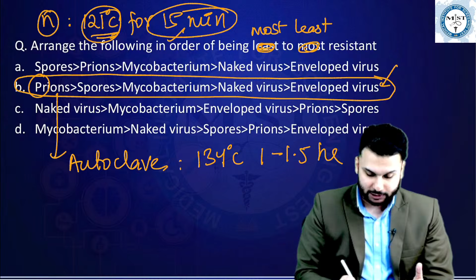But now, when we are talking about something very resistant called prions, this will not be enough. That means the temperature of 121 cannot be enough. So I will increase the temperature in the autoclave to 134 degrees, and that too not for 15 minutes. I will increase the duration to 1 to 1.5 hours. Prions, sir. Prions will not die so easily. So you need to sterilize for a long time, at least 1 to 1.5 hours. Done? This was the autoclave.